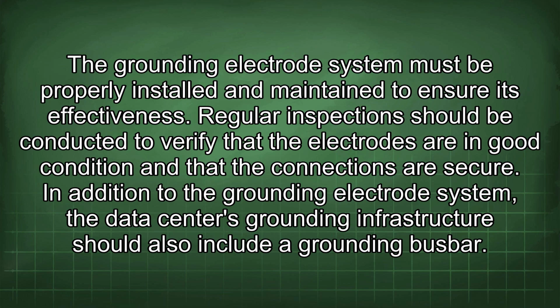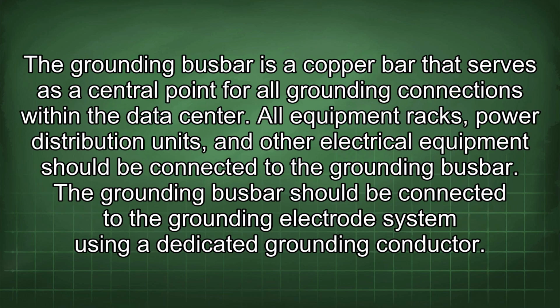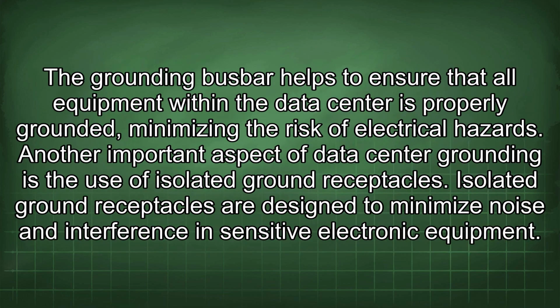In addition to the grounding electrode system, the data center's grounding infrastructure should also include a grounding busbar. The grounding busbar is a copper bar that serves as a central point for all grounding connections within the data center. All equipment racks, power distribution units, and other electrical equipment should be connected to the grounding busbar. The grounding busbar should be connected to the grounding electrode system using a dedicated grounding conductor. The grounding busbar helps to ensure that all equipment within the data center is properly grounded, minimizing the risk of electrical hazards.